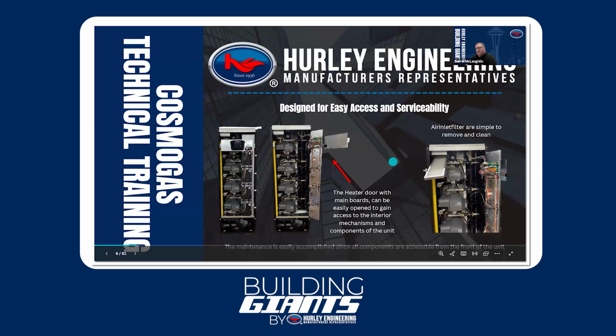So then again, if you look over here, they also provide filters that come with every unit. That's a standard item. So whether you're doing outside air or you're just using room air for your intake air, it's going to be filtered, and we're going to use this cabinet like a plenum to deliver air to each one of our burners. And we want to deliver the cleanest air possible. It helps protect the heat exchanger, protect your burner, protect your fan motor, or your blower wheel, all those things.